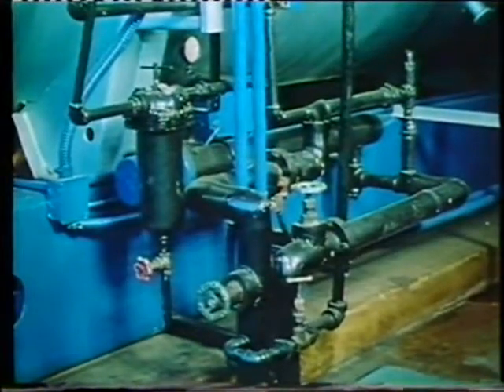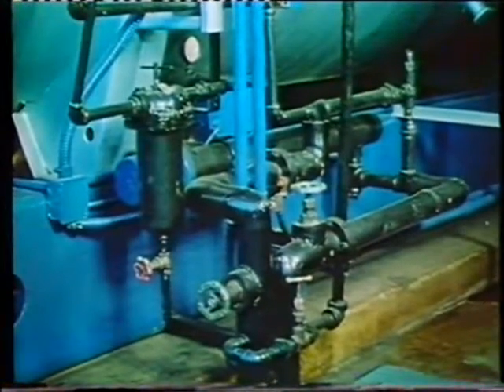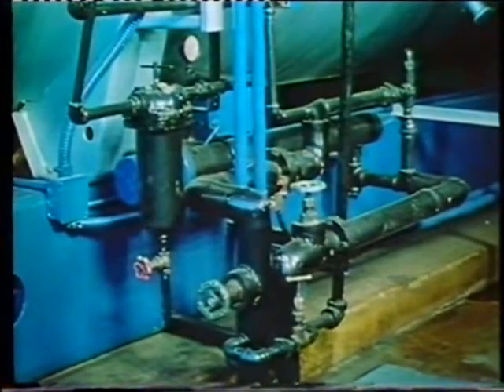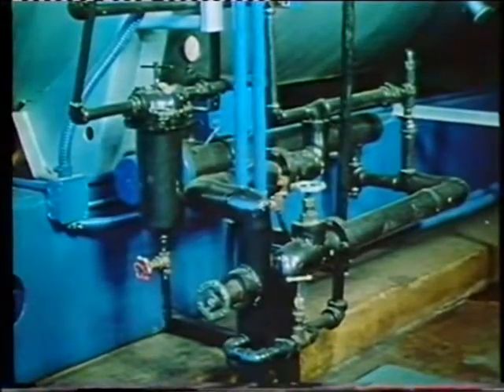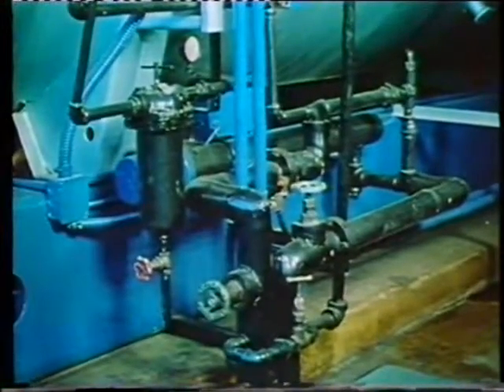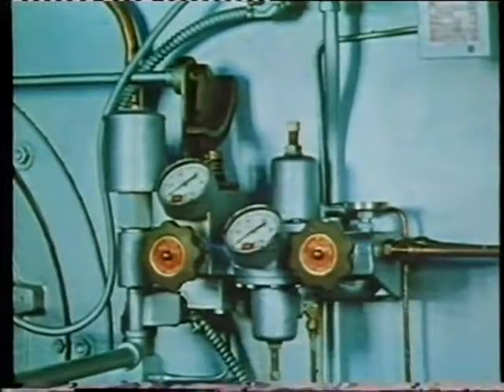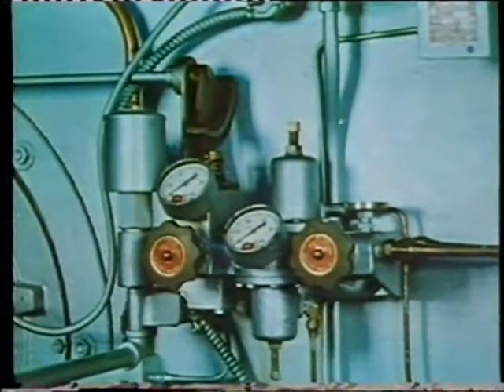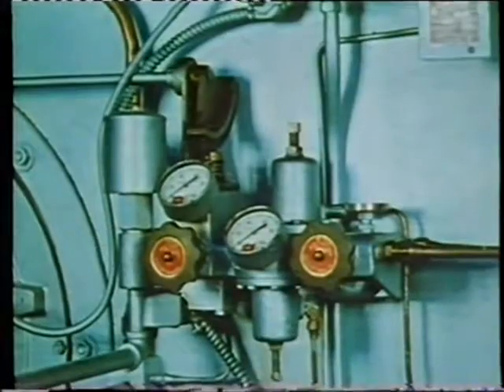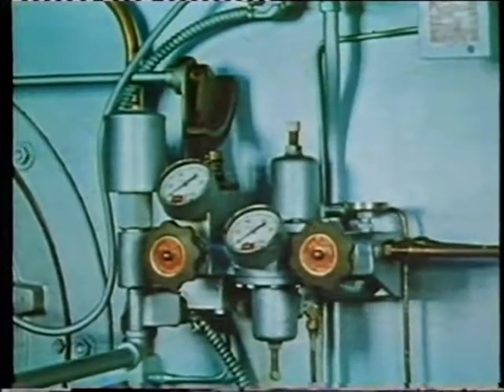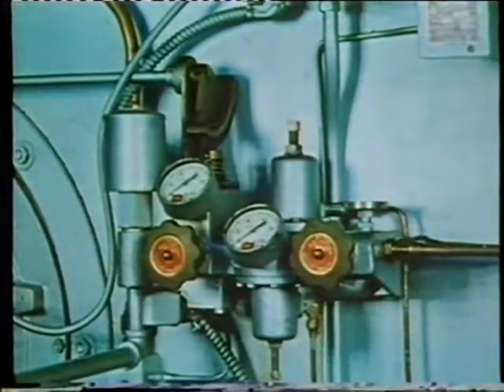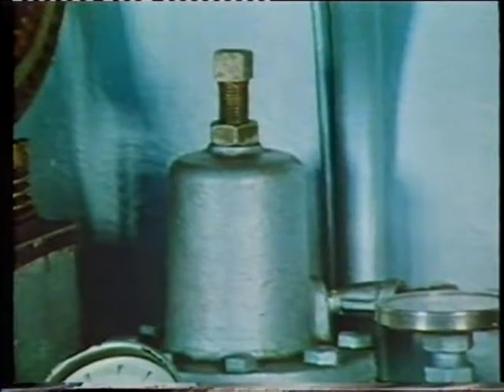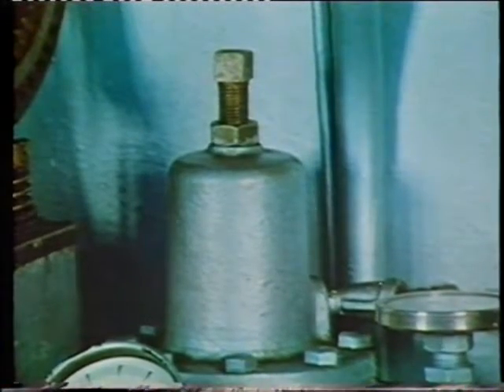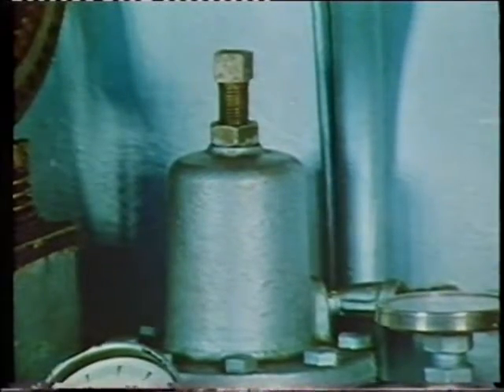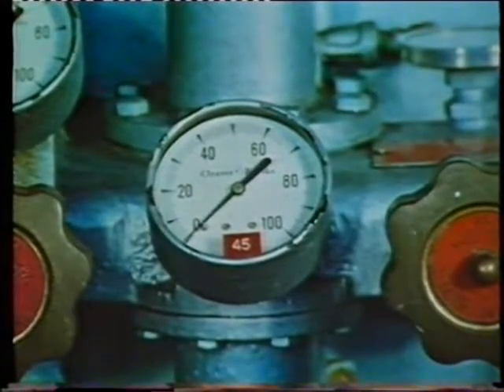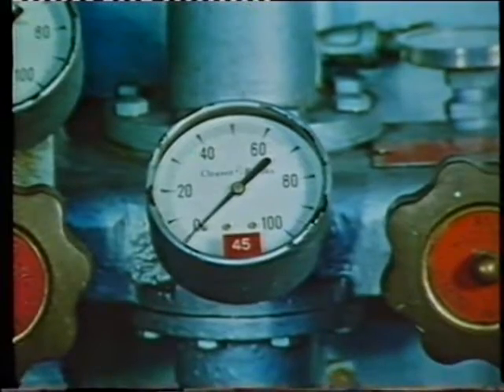The combination of fuel oil controls at the boiler is called the fuel train and may include another strainer, heater, relief valve, and other devices. Various manufacturers will use different control assemblies. The fireman must know the fuel control assembly for his particular boiler. The pressure regulator controls the pressure of the oil at the metering valve. The fuel pressure gauge indicates the pressure at the metering valve.